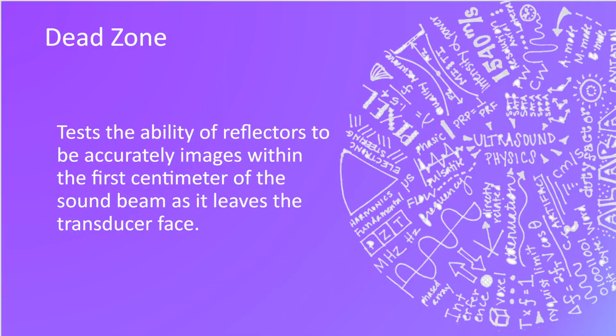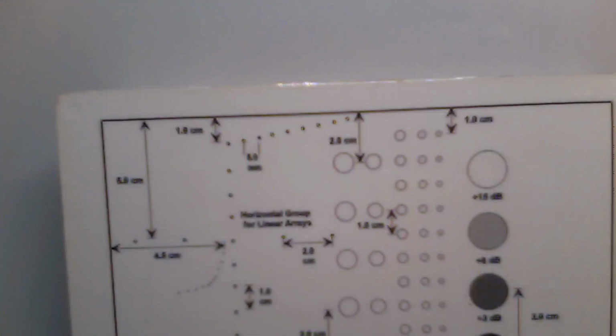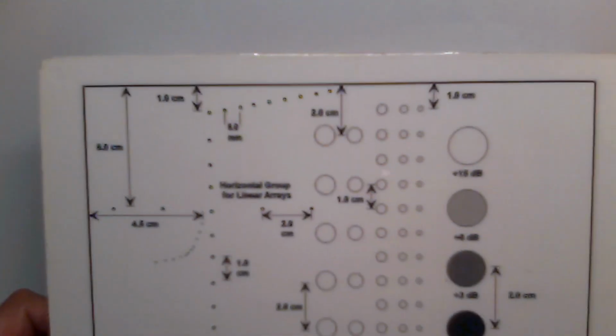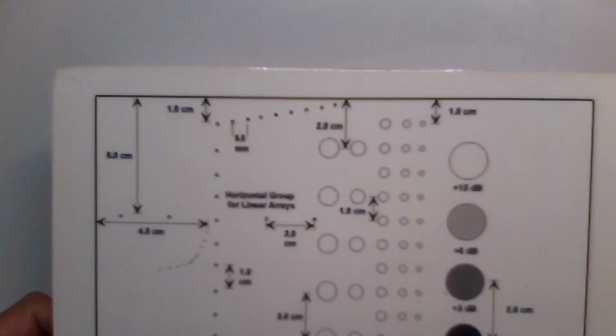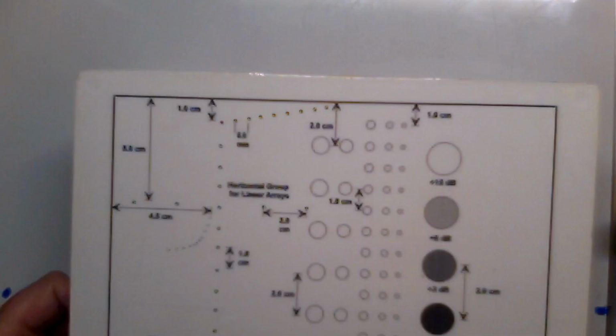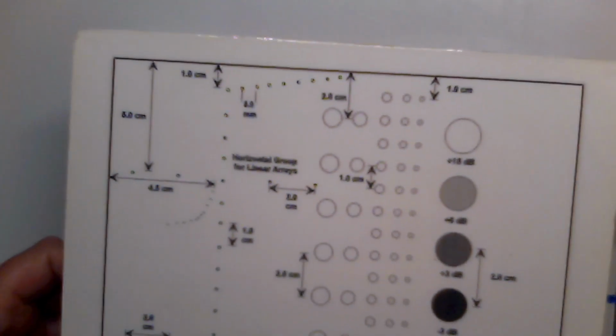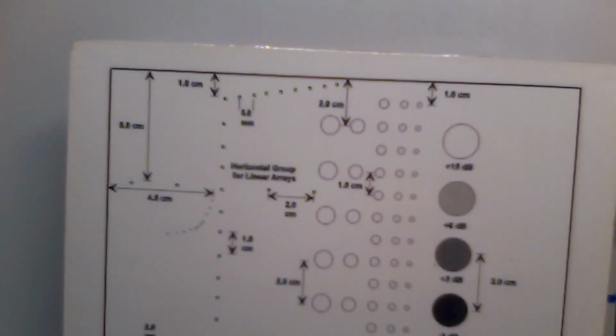The next thing that we can test with the tissue equivalent phantom is the dead zone. And we talked about this a little bit. We want to test the ability of reflectors in those first few centimeters to be displayed. Just getting out the phantom again here. We'll head over to that side. So, that's a little blurry. It'll work. Okay, so we have our dead zone.